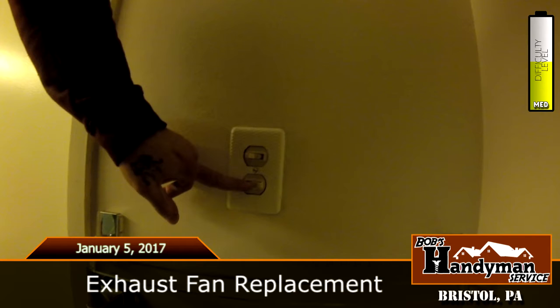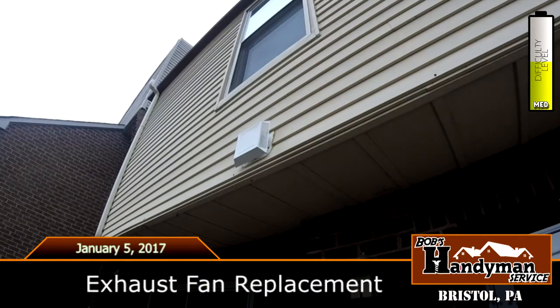Because what happens in some cases, power is run to the unit first and then sent down to the switch and back to the unit using the switch as an intermediary between the two. When you do this, even shutting the power off to the switch will leave a live wire up in the box. So always use the circuit breaker box if you're unsure of how it's wired. In this particular case, I know for a fact that this is wired to the switch first, and therefore there will be no electrical current while working on the project.